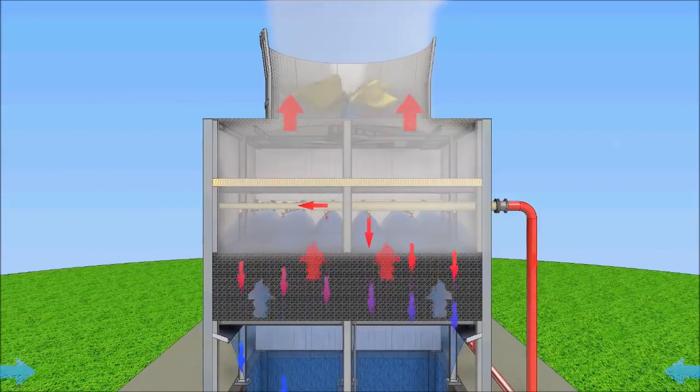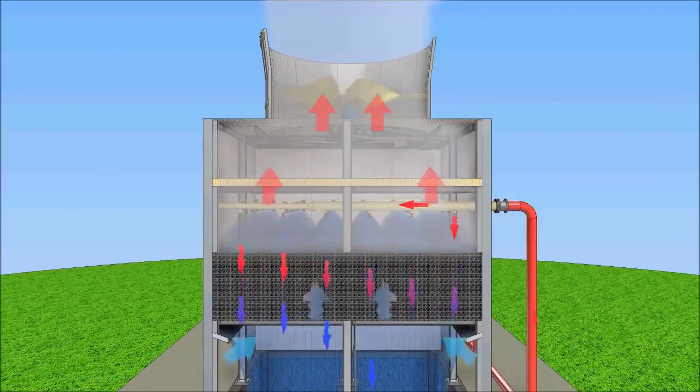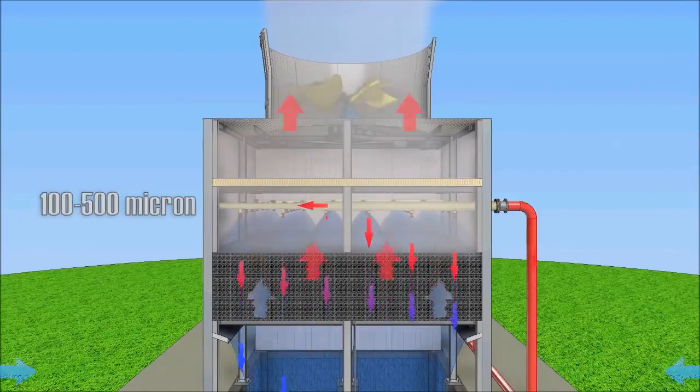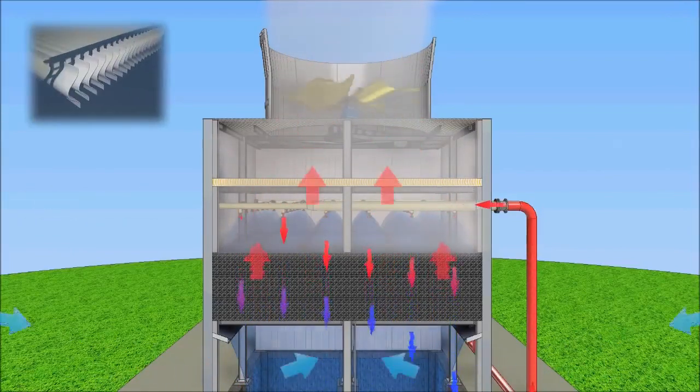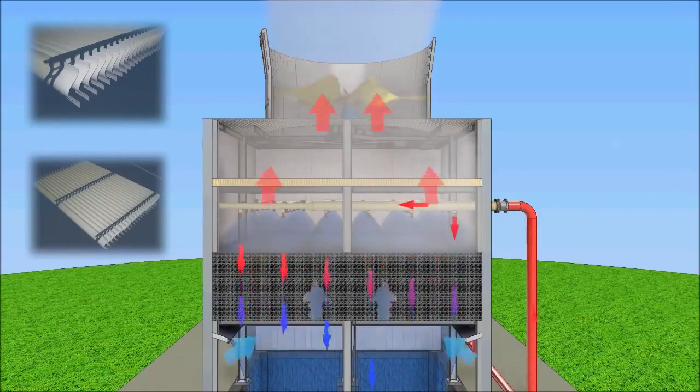During cooling tower operation, air saturated with water vapor contains water droplets with sizes of 100 to 500 microns. To prevent drift and water droplet loss, a drift eliminator system is installed.